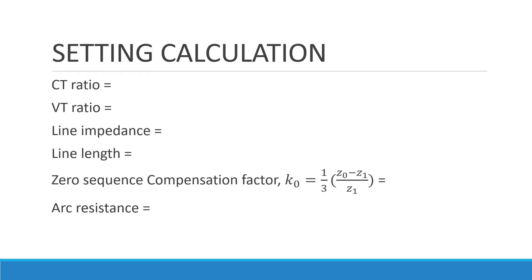To configure a distance relay you need to know the CT ratio, the VT ratio, the line impedance, the line length, and the zero-sequence compensation factor. The zero-sequence compensation factor is used to translate the zero-sequence impedance to the positive sequence. The arc resistance and tower footing resistance are also necessary in the case of a ground fault. Next we will go to ETAP and see how to implement distance relays. If you are interested in knowing more about distance relays, I will attach additional resources with this lecture.